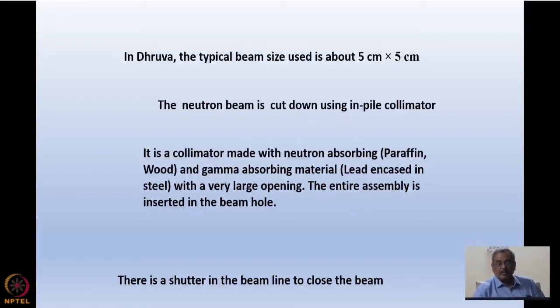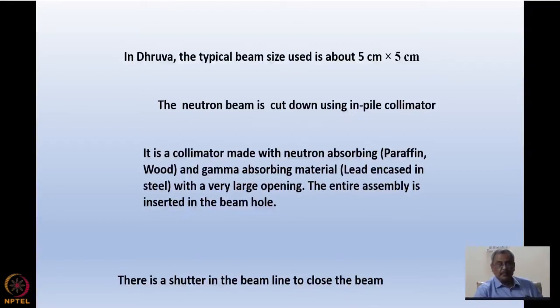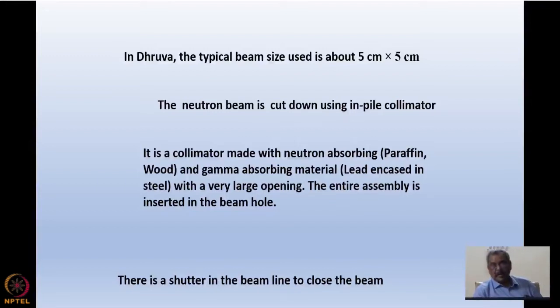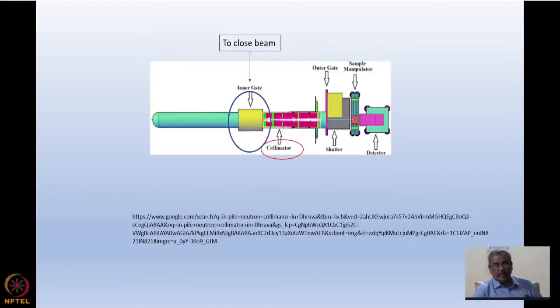The neutron beam is first cut down using an in-pile collimator in the beam path. The name itself indicates it is inside the pile — inside the biological shielding — inserted in the biological shielding so that we take out only the desirable beam size; the rest we try to cut down right inside the beam tube. This collimator is made with neutron-absorbing materials — paraffin, wood — and gamma-absorbing materials like lead encased in steel or even steel itself, with a large opening of at least 5 cm × 5 cm. There is also a shutter in the beam path to close the beam.